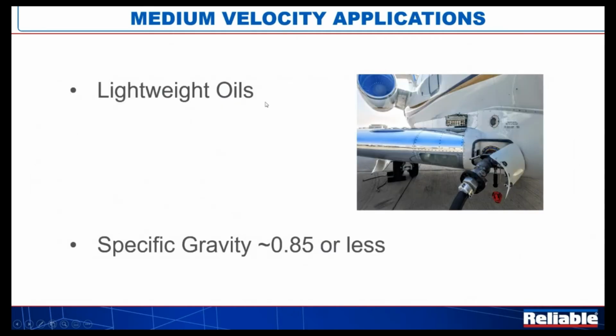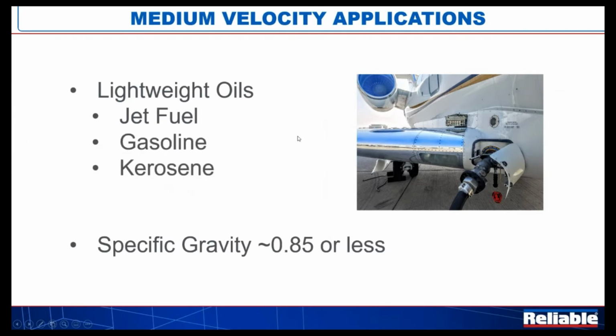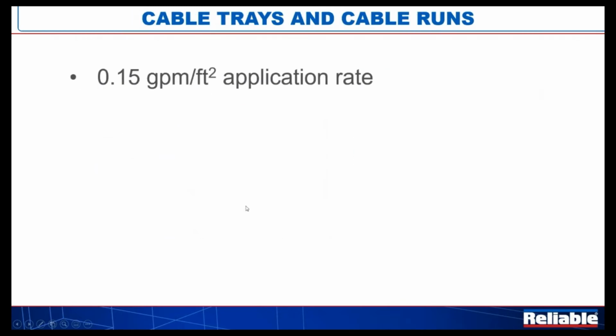So again, where are we using those? We're using those on lighter weight oils, specific gravity around 0.85 or less. And where do we see those? Jet fuel, gasoline, kerosene, and again, medium velocity nozzle applications would be used for that dispersion and dilution of vapors. So let's talk now about the common protection uses that come out of NFPA 15. Cable trays and cable runs, we're going to get into a little bit of detail. We'll go through these pretty fast right here.